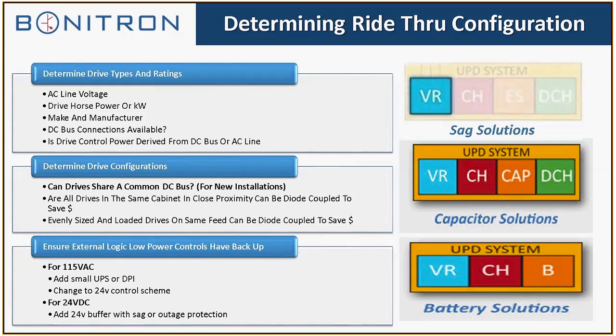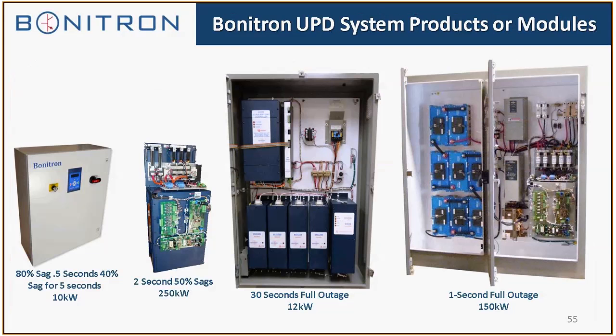And just some of the control power schemes that we deal with. For 115 volts, you might want to add a small UPS or dip-proof inverter. And for 24 volts, we have a full line of either full outage backup or SAG outage backup. And that's dealing with control power in 24 volt or 115, 120 volt.